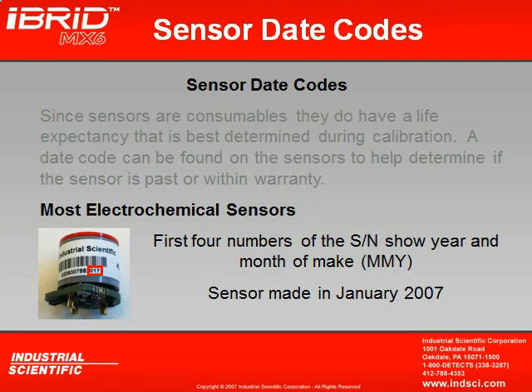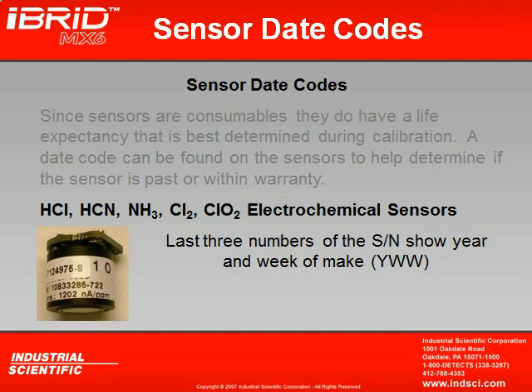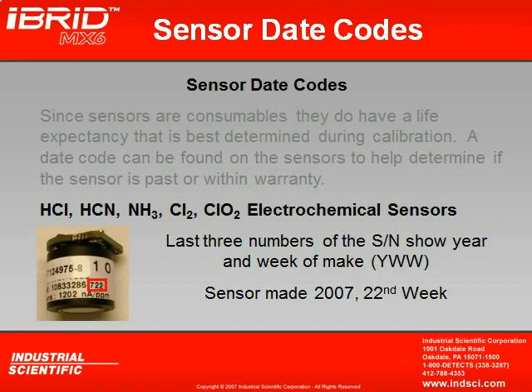Now for some of your more exotic toxics, gases like hydrogen chloride, hydrogen cyanide, ammonia, chlorine, chlorine dioxide, the way you read the date code in these sensors is a little bit different. Once again, you're going to use the last three numbers, but it goes year and week of make. So what we see here is the sensor was made in 2007. That's what the 7 would indicate, and the 22 would indicate the 22nd week.